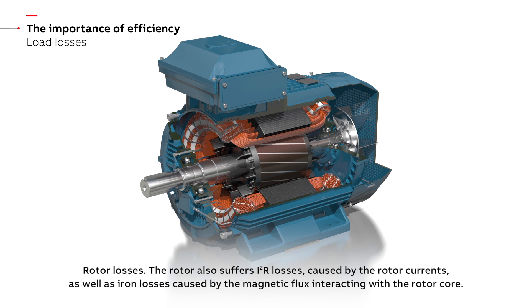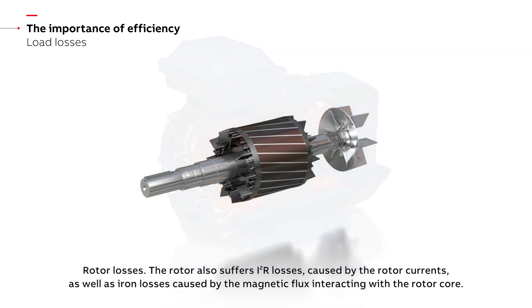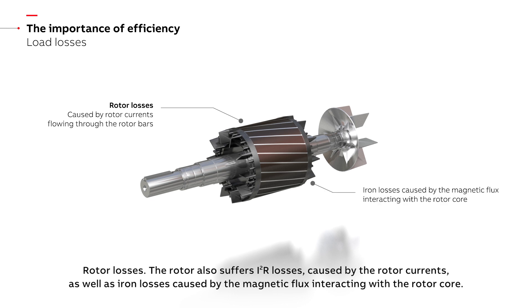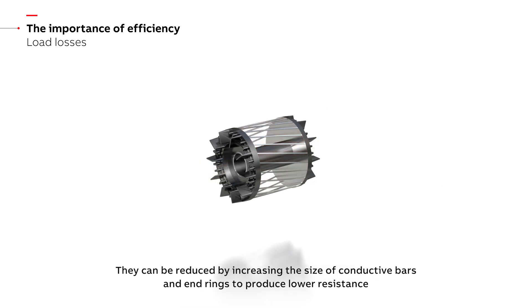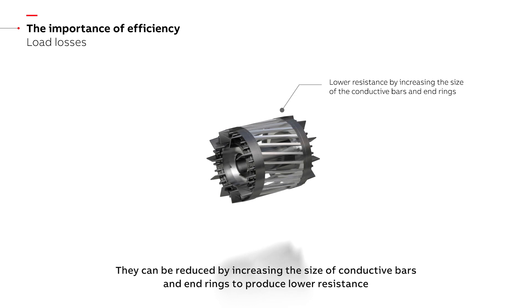Rotor losses: the rotor also suffers I squared R losses caused by the rotor currents, as well as iron losses caused by the magnetic flux interacting with the rotor core. They can be reduced by increasing the size of conductive bars and end rings to produce lower resistance.